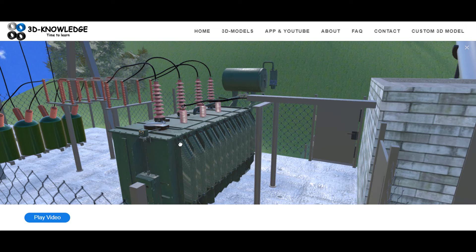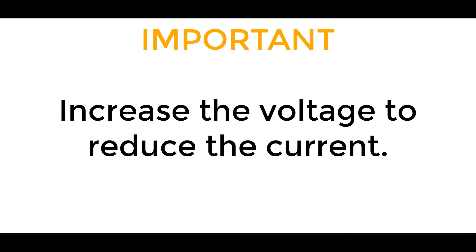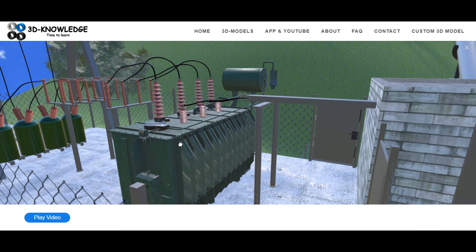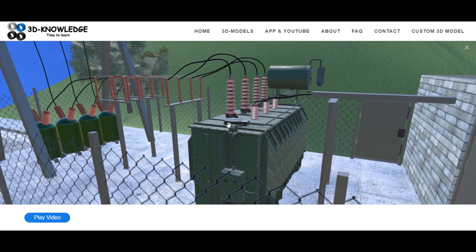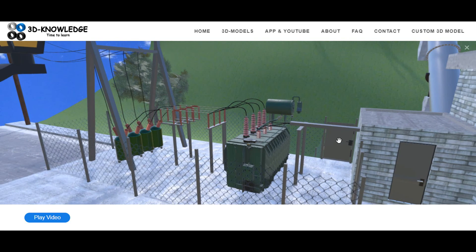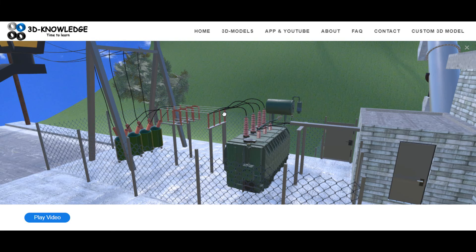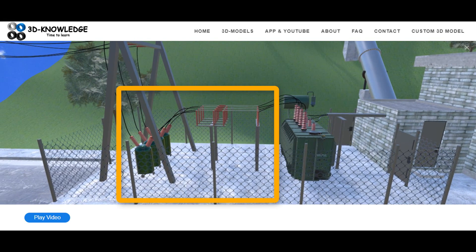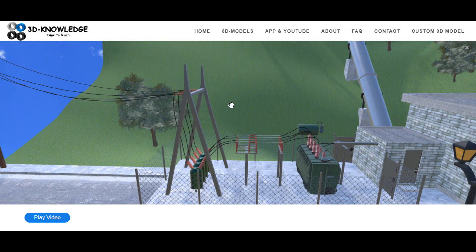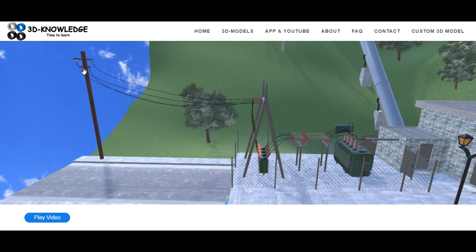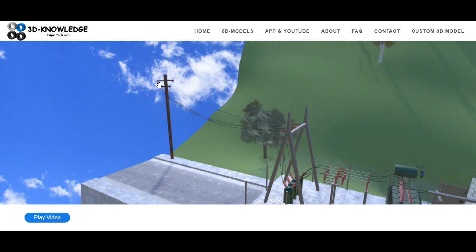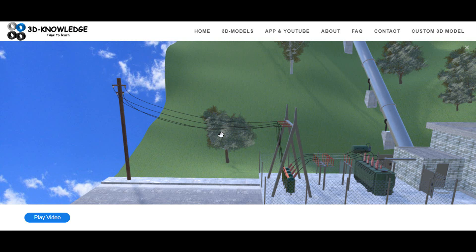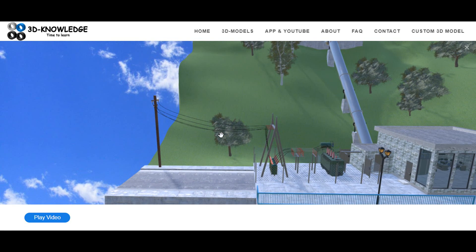Now there's a relationship between power, current and voltage. But imagine for a moment that in your car you've got a 24 volt cable for batteries or a 12 volt cable. These cables are actually quite thick. Now that's only for 24 or 12 volts, but the reason they're thick is because they carry a high current. So if you can step the voltage up and reduce the current, then you can have thinner cables and this is a massive benefit if you've got hundreds of kilometers of cables. In addition to that, the losses that you'll have on your transfer grid or on your network will be lower if you step the voltage up. That's exactly what the transformer does. It will step this up to say for example 110,000 volts, 110 kV, and it will then go through an open air switchyard which is this area here and perhaps pass another circuit breaker, and then it will connect to the national grid. You can see it connecting to a pole there and that will go off into the distance, connect to another transformer to step the voltage down again and we could use it for power in our homes such as for the dishwasher or the microwave.